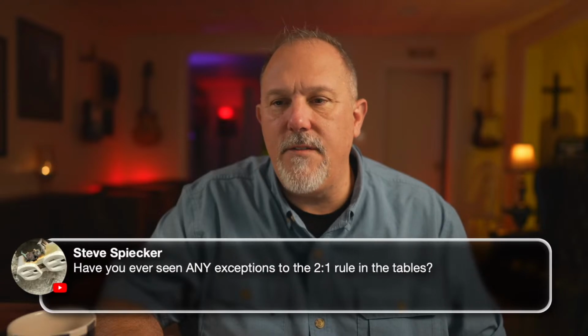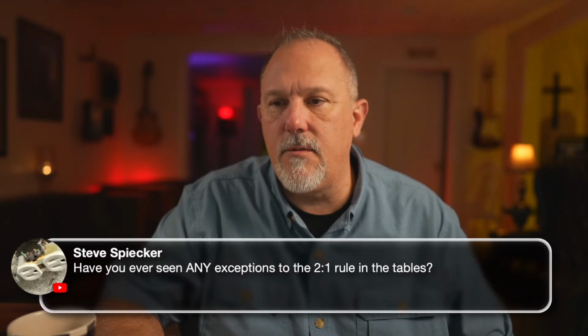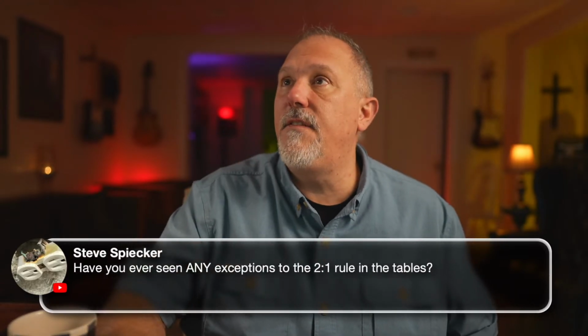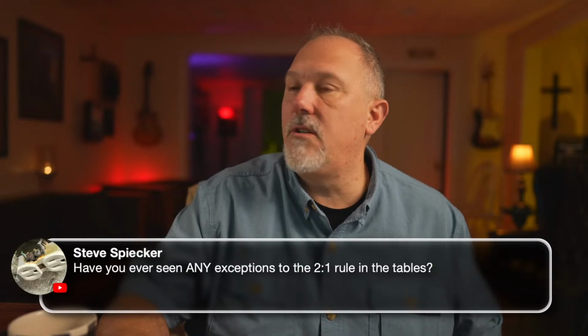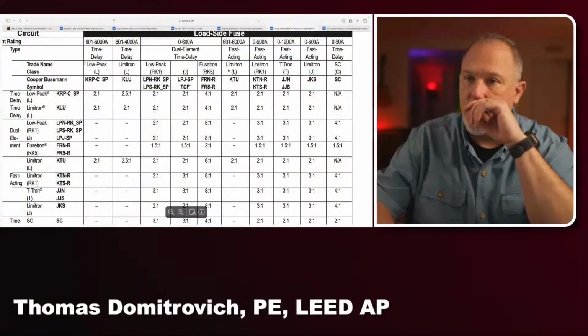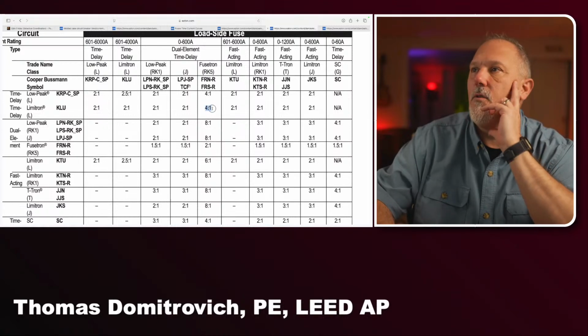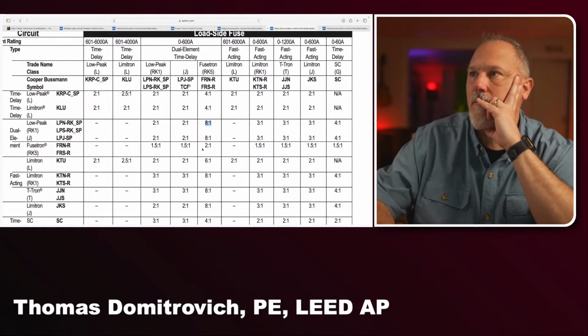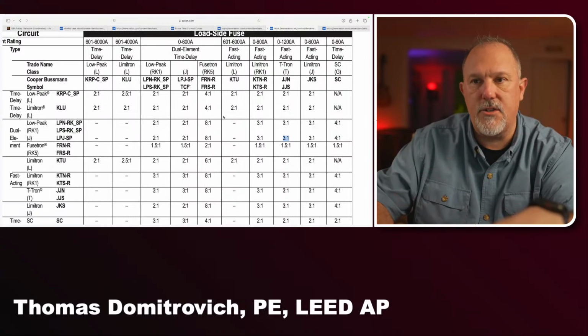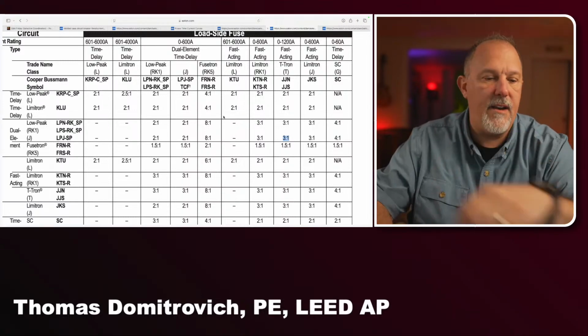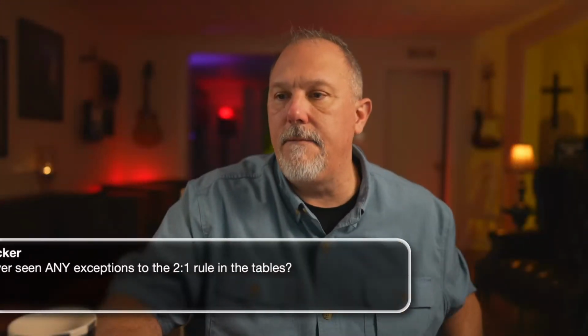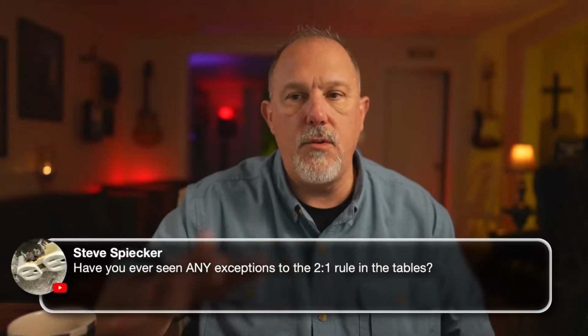Steve, have you ever seen any exceptions to the 2-to-1 rule? Yeah, I did. There are some exceptions to the 2-to-1. It's in the tables. So you've got 4-to-1, you've got 8-to-1, 3-to-1. Depending upon what you have upstream and downstream, you'll have different requirements. So you've got to make sure you use the tables correctly.